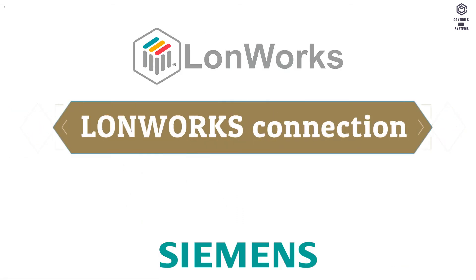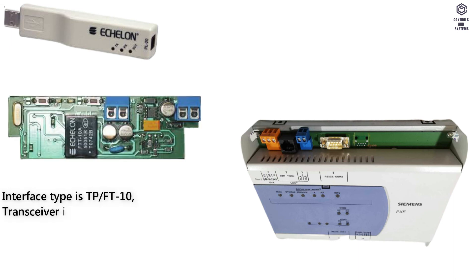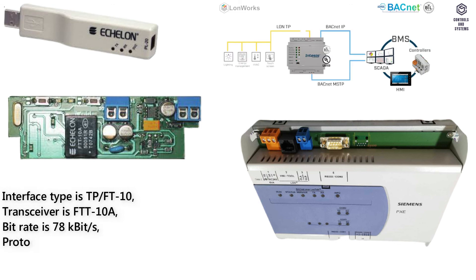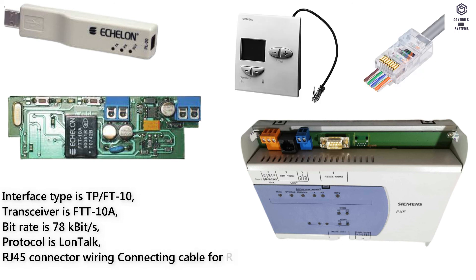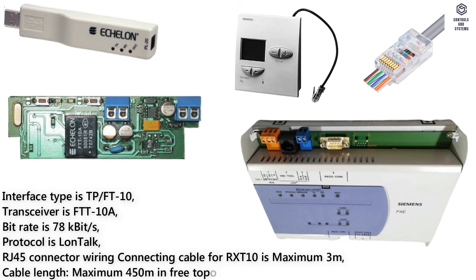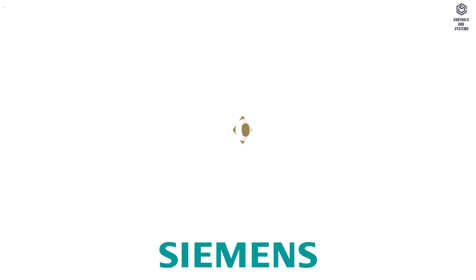LonWorks connection, blocks 51 and 52: interface type is TP-FT10 for RXT10, transceiver is FTT10A, bit rate is 78K bit/s, protocol is LonTalk. RJ45 connector wiring, connecting cable for RXT10 is maximum 3 meters. Cable length: maximum 450 meters in free topology or maximum 900 meters in serial topology.